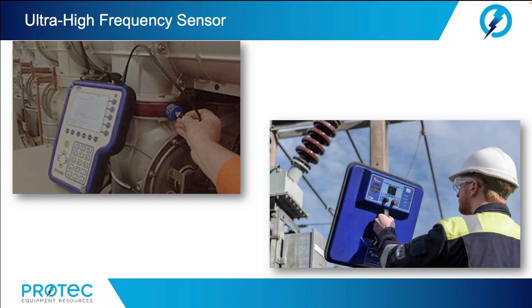All types of partial discharge will produce electromagnetic emissions in the UHF range. In most cases, the UHF emission is detectable with the UHF sensor. The UHF pulses are going to be emitted from the site of the PD defect and will spread in all directions through air and through most materials. However, the signal cannot travel through metal. Metal enclosures will shield the UHF emission. The signal can escape through tiny cracks, gaskets, and seals, and then spread out into the air.